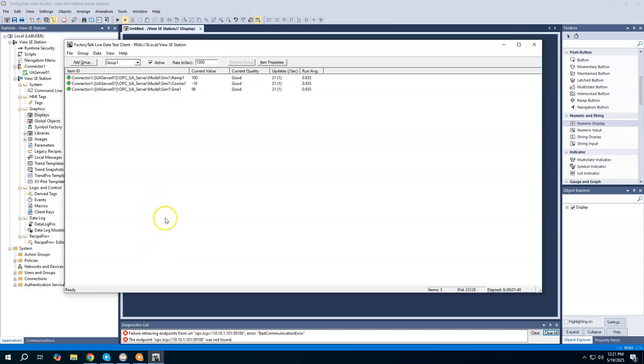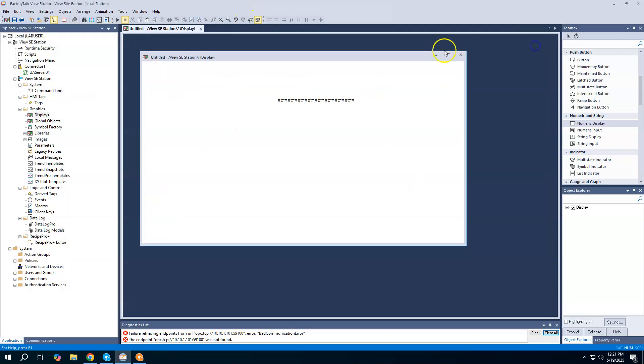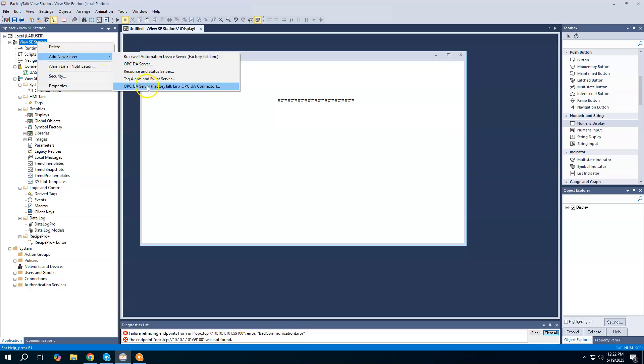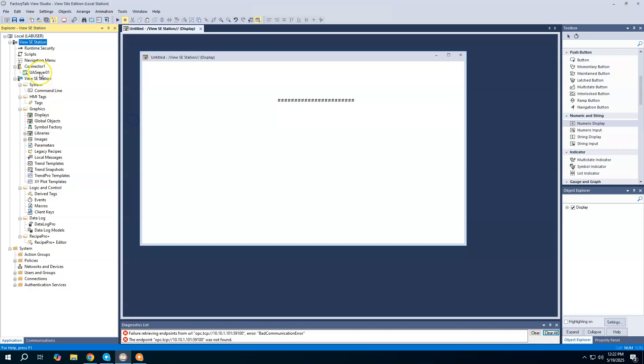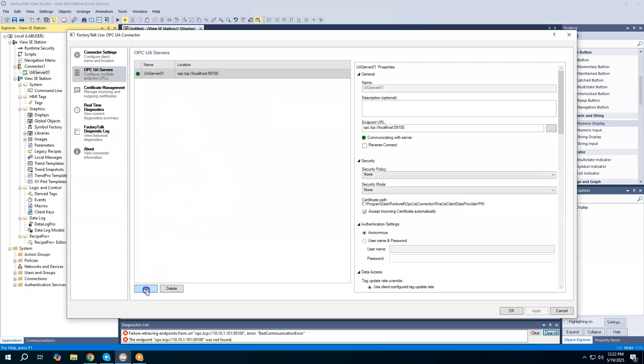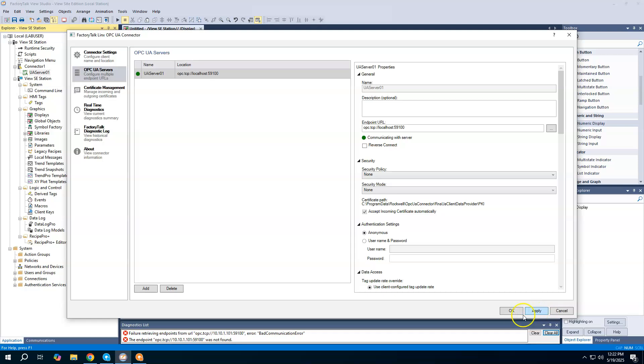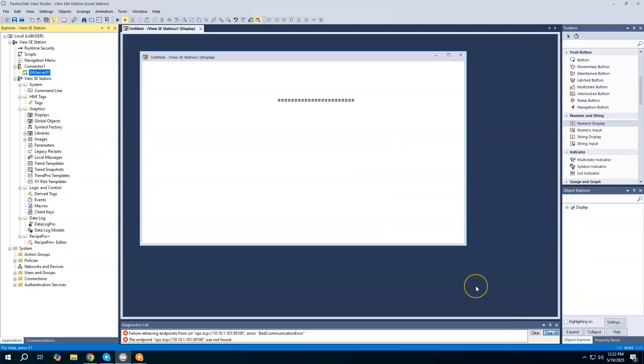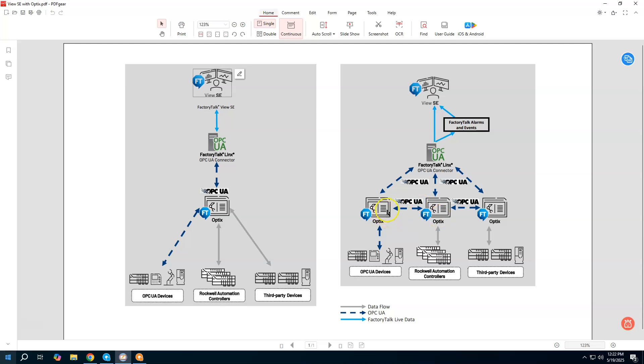Just wanted to show how we go about using the OPC UA connector in FactoryTalk View SE. We're going to come up here and add a new OPC UA server. We could come back to connector one, and we could actually add an additional server, a server two if we wanted to. We can add more than one UA server. We're not just bound to just one coming from one Optix. That kind of gets us back to when we look at our picture here. Here we have three separate Optix applications, each acting as an OPC UA server. This FactoryTalk Linx OPC UA connector would have one connection here, another server connection here and a third server connection here. So we can do multiple or we can aggregate into one single.